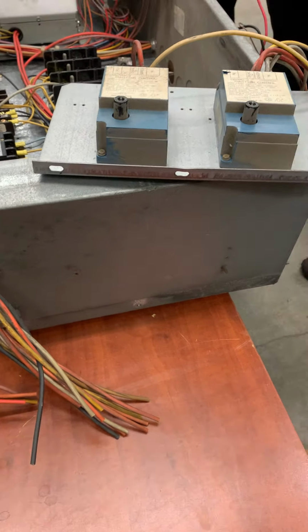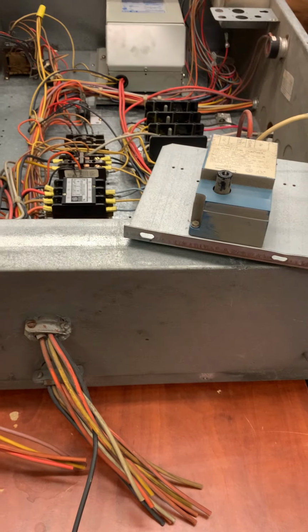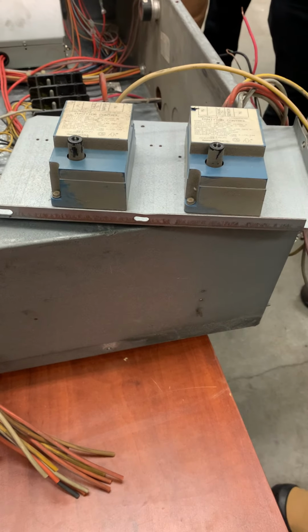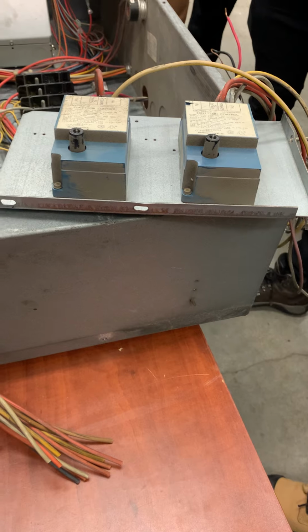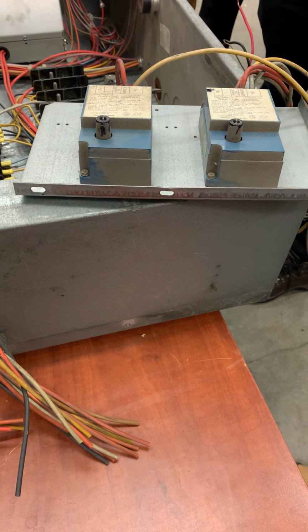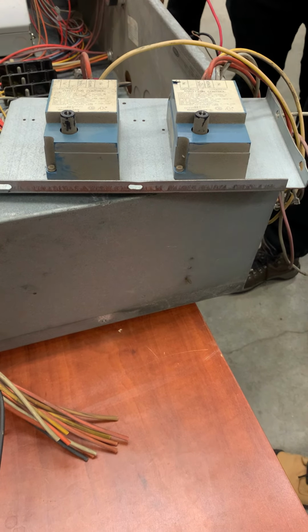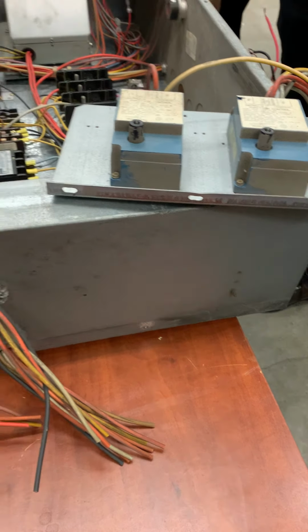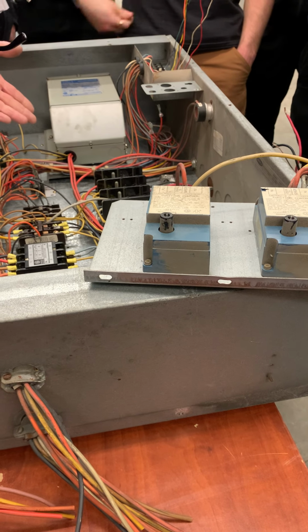What's another way you know that the sheet metal is the ground on the 24 volt side? Look at the transformer. I got one wire off the transformer going right to ground. So I now know that the 24 volt side is grounded. And this is part of the equation where you look at other parts that you've seen and apply them to what we've seen here.